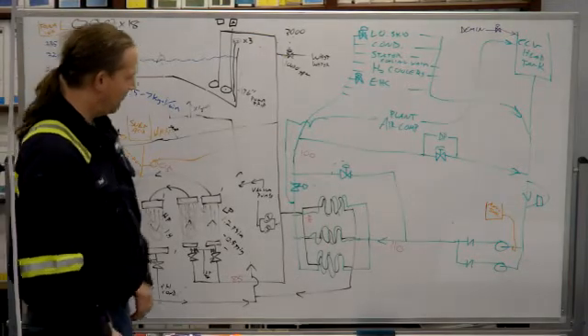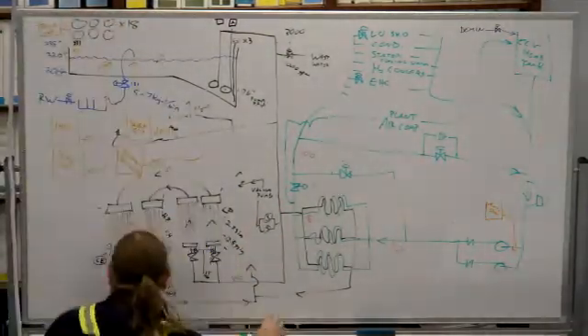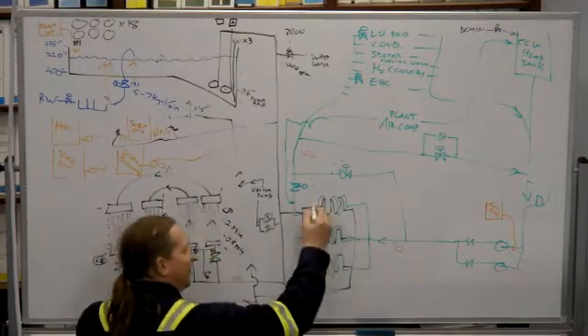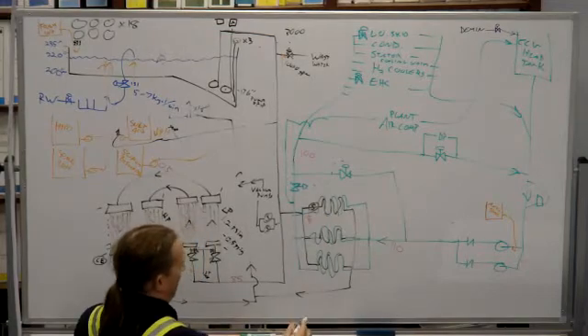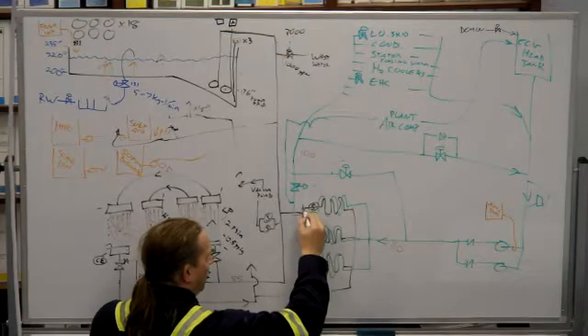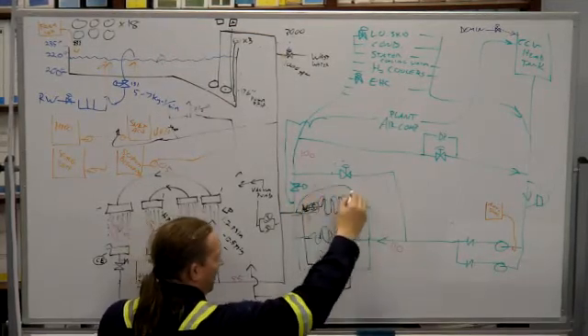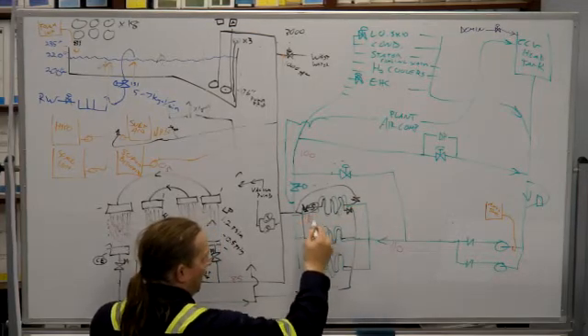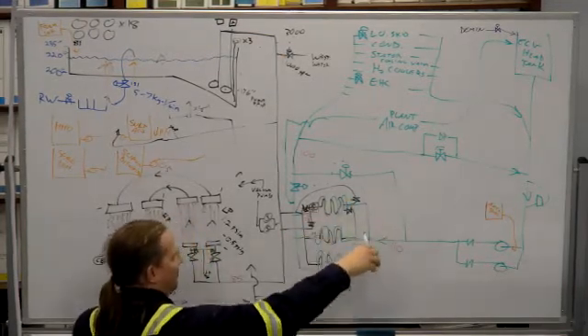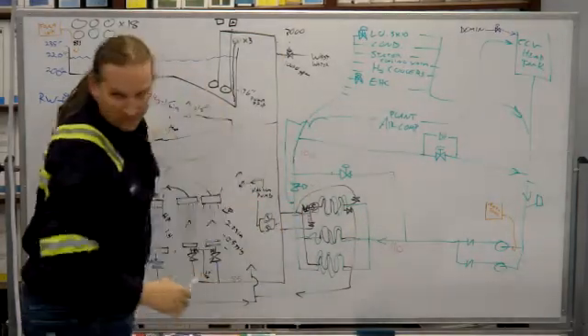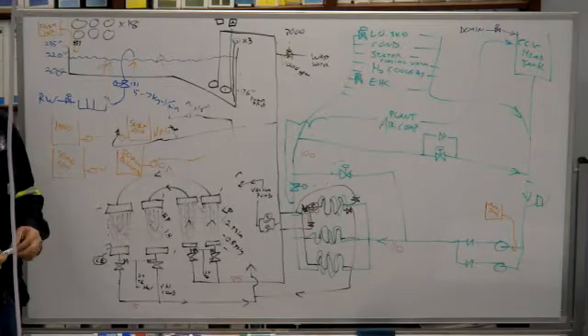Backwash. I'm not sure if this should have been in the circ water part, because it was actually on the circ water side that you're doing the backwash. But on the inlet side of each of these heat exchangers, there is a strainer. And there is a piping arrangement where you shut the normal inlet and outlet. And then you line up an alternate inlet and outlet that runs through it backwards. So that everything in that strainer gets washed out and goes back to the cooling tower.